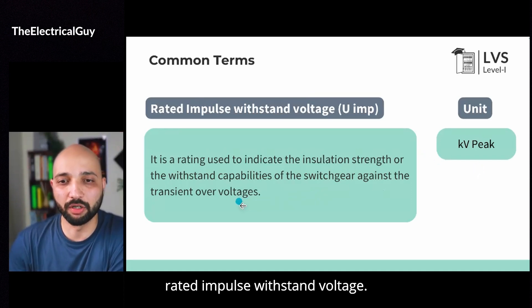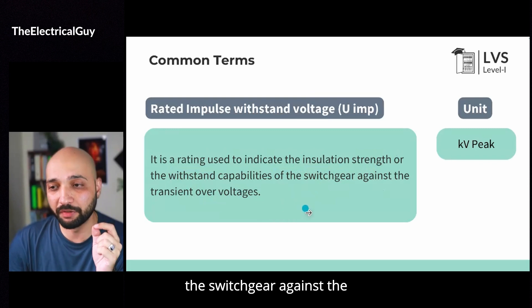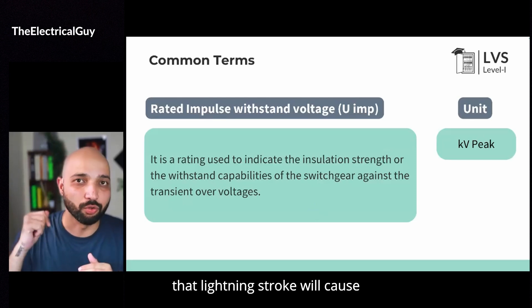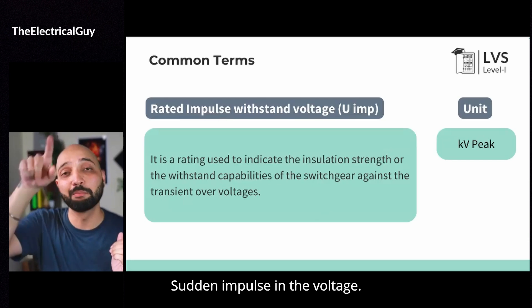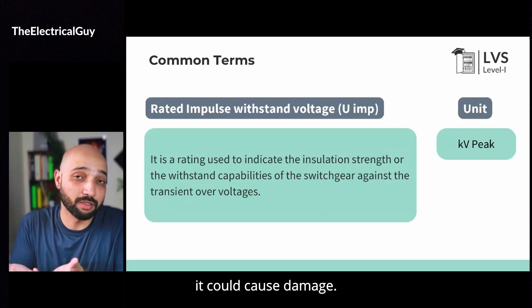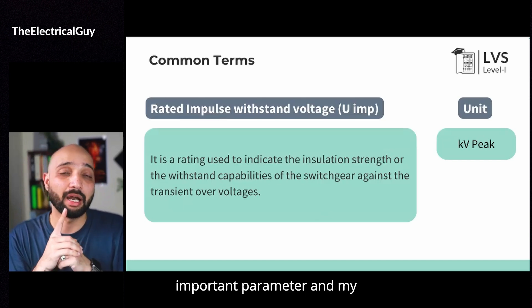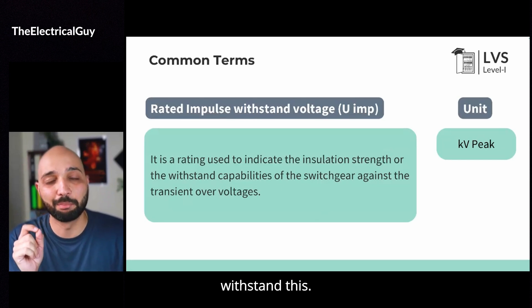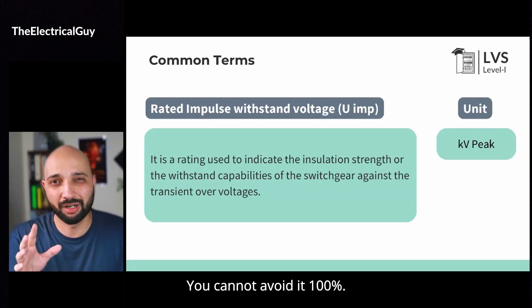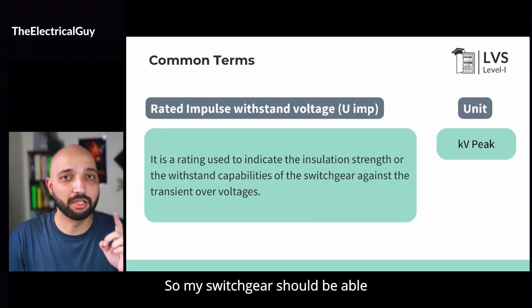Now let us understand what is rated impulse withstand voltage. It is the rating used to indicate the insulation strength or the withstand capabilities of the switchgear against transient overvoltage. There can be a situation — let's say there is a lightning stroke. That lightning stroke will cause a sudden impulse in the system, a sudden impulse in the voltage. My switchgear should withstand that. If my switchgear is not withstanding that, it could cause damage. My switchgear will burn down and that fault will replicate into different systems. So certainly it's a very important parameter and my switchgear should be able to withstand this impulse — these transients that are coming into the system. These are inevitable; they will come for sure. You cannot avoid them 100%, you can surely reduce the amount, but they will come into the system.